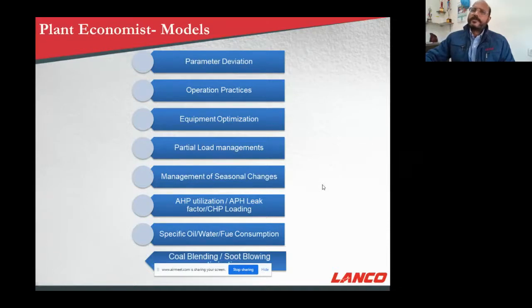Similarly, specific oil consumption in the plant, fuel consumption, and diesel consumption in the entire plant. Lubrication oil consumption, maybe annually in the plant. So water, specific water consumption. These parameters, this information is captured and their relationships are established based on the measurement done at the site, on the best achieved and or the design recommended. Then coal blending as well as soot blowing.